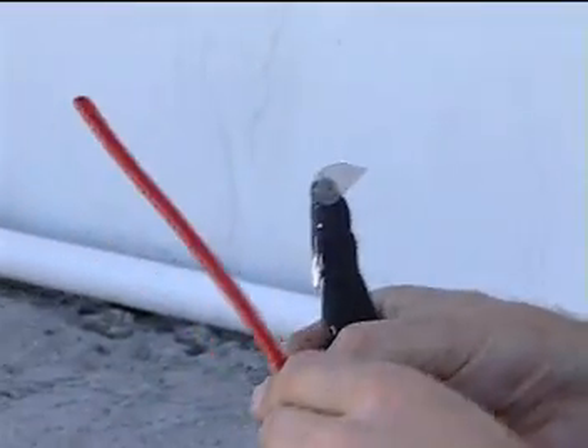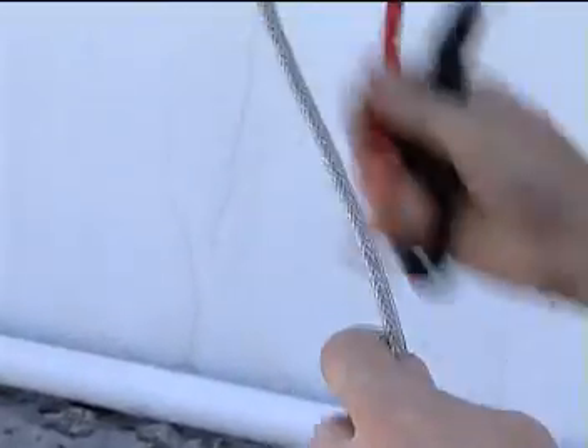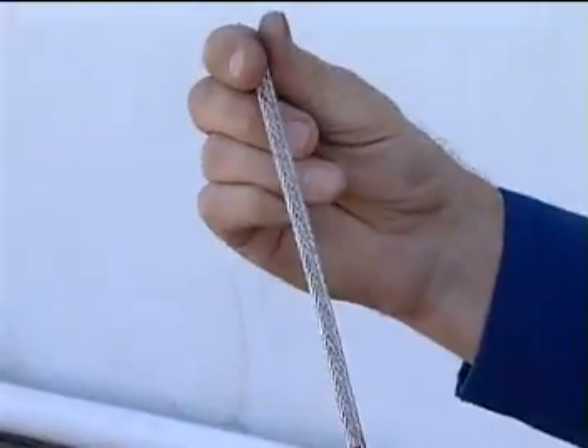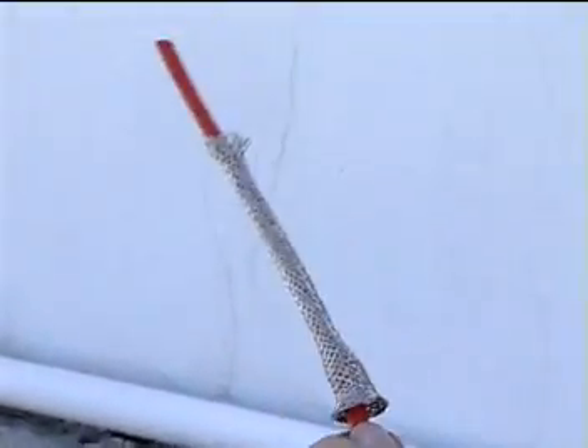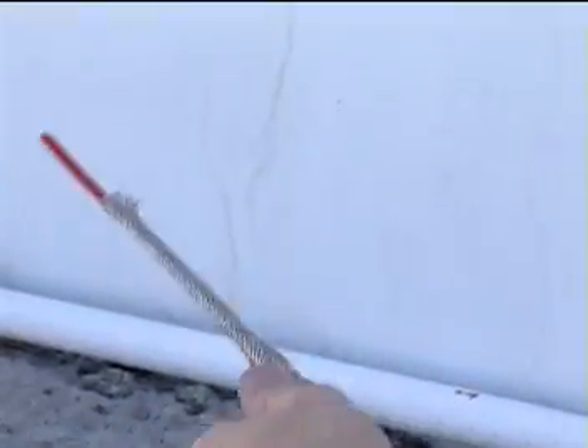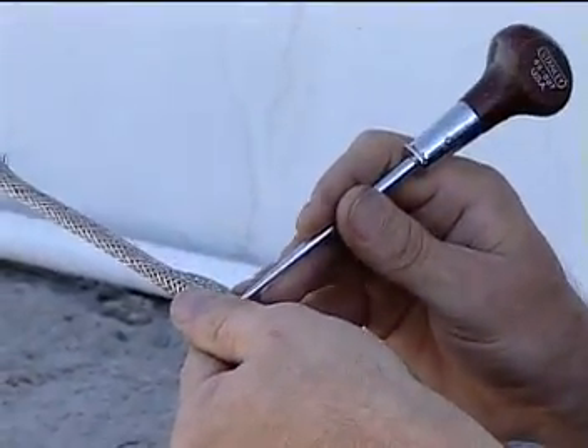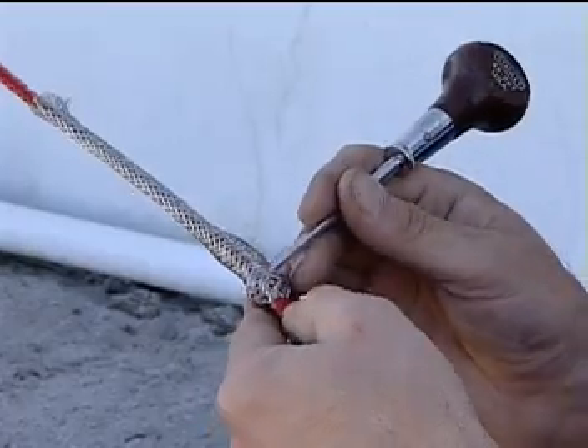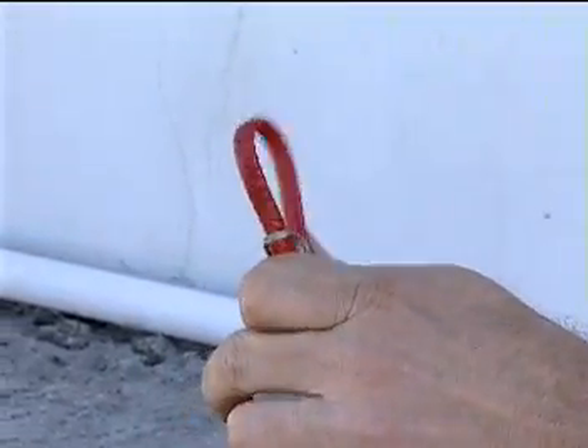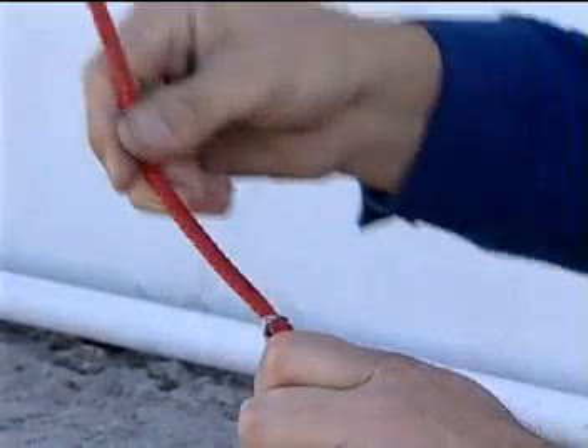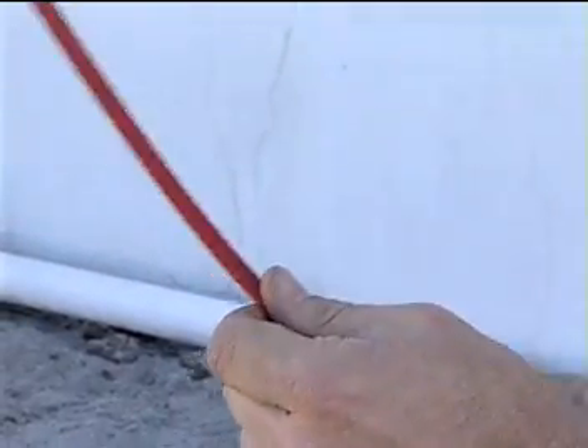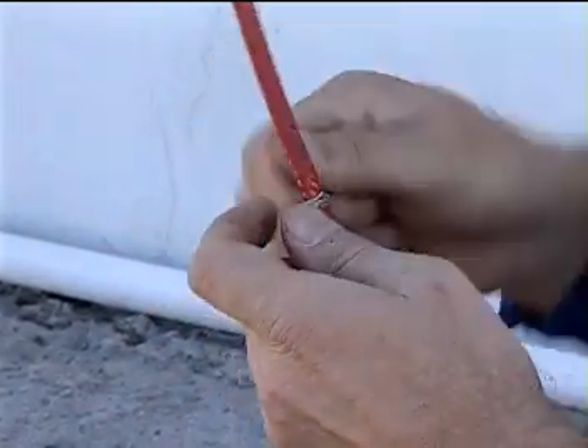When stripping the XTV CT cable, use Raychem's jacket stripping tool or utility knife to remove the outer jacket, being careful not to cut the braid. Then take an awl and make a small window in the braid and bend the cable. Use the awl to work around the cable and open up enough of the braid to pull the cables all the way out. Then bend the braid back out of the way.